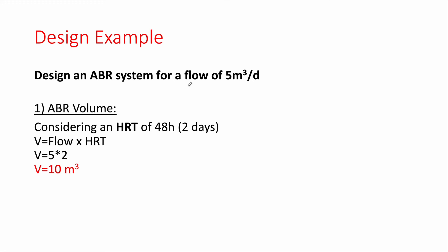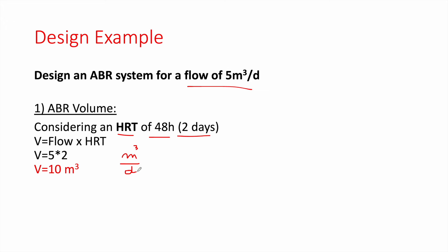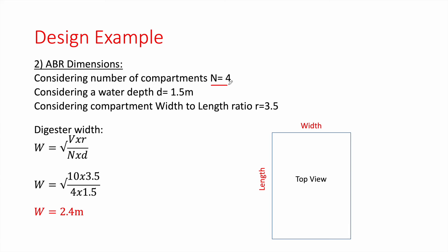In the practical example, we design an ABR system for a flow of 5 cubic meters per day. First, find the ABR volume by assuming a hydraulic retention time of 48 hours, which equals 2 days. Volume = flow × HRT = 5 m³/day × 2 days = 10 cubic meters. This is the total volume of all the vertical baffles. We then choose 4 compartments and a water depth of 1.5 meters.